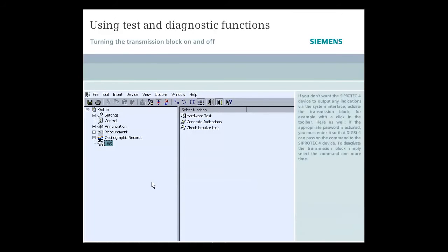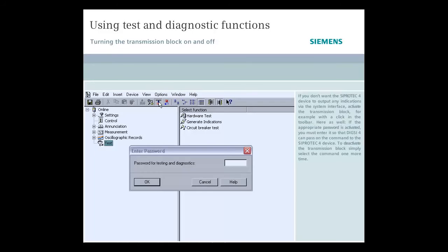If you don't want the SIPROTEC 4 device to output any indications via the system interface, activate the transmission block either with a menu command or with a click on the symbol in the toolbar. Here as well, if the appropriate password is activated, you must enter it so that DIGSI 4 can pass on the command to the SIPROTEC 4 device.